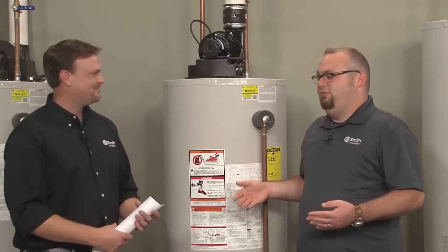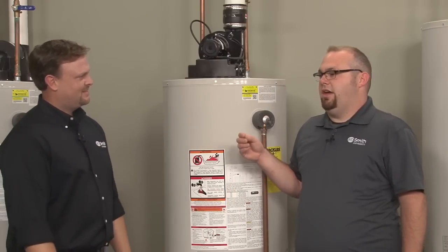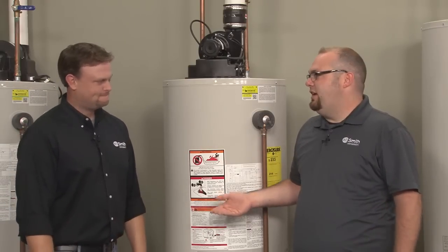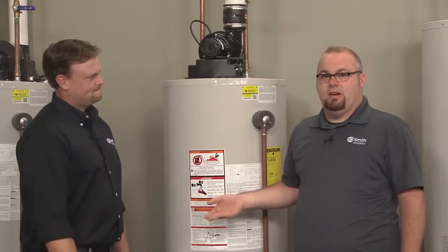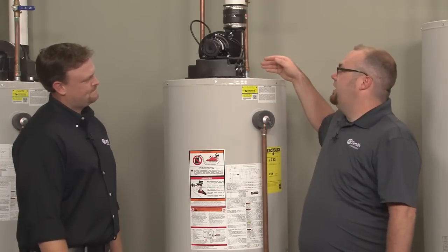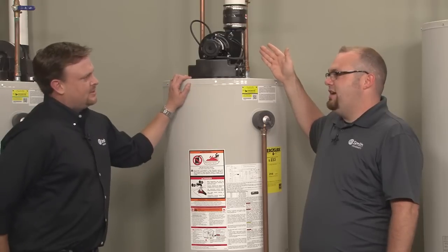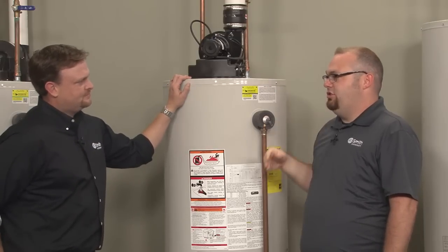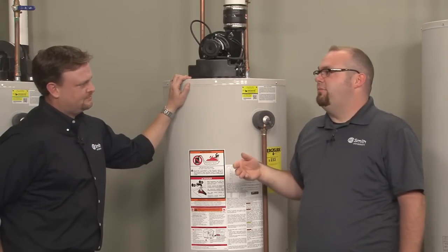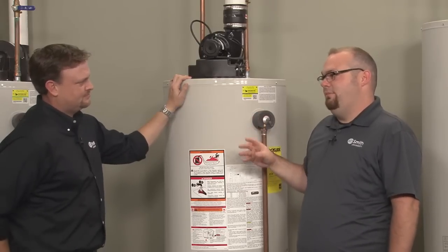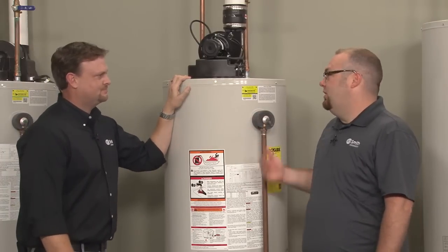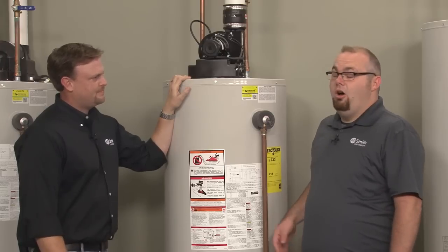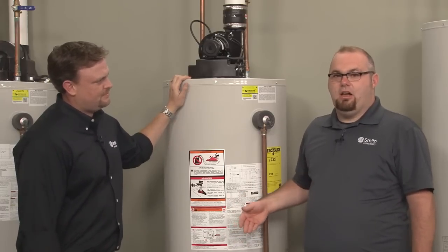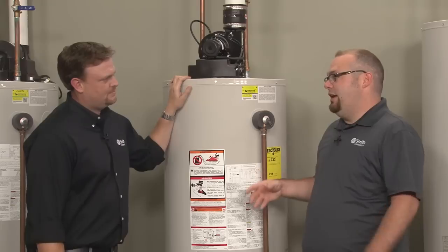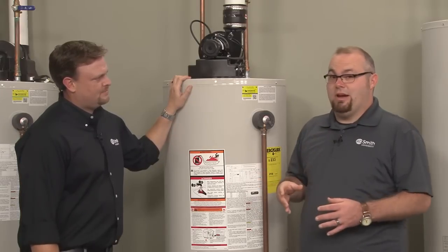Right? In a lot of cases, a 90-degree elbow, if it's just a 90, could count as 5 feet. A 45 counts as 2.5 feet. So if you can only run this heater 20 feet, but use a 90, that means you can use 15 feet of straight pipe. Some people will think, well, I can use 20 feet of pipe, then the 90. That's not the case. It will not close the switch. And always while you're checking the venting, also make sure you're using the right termination screen on this one, or at least the right termination.